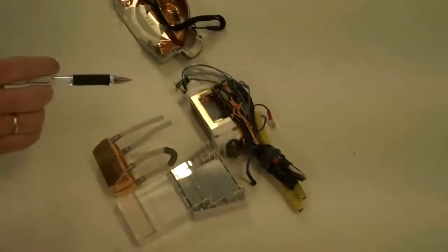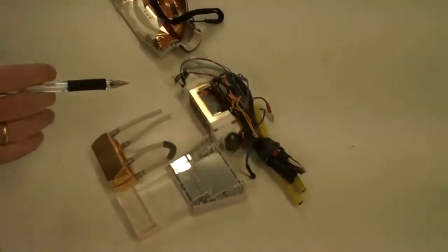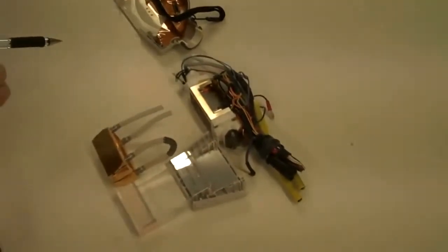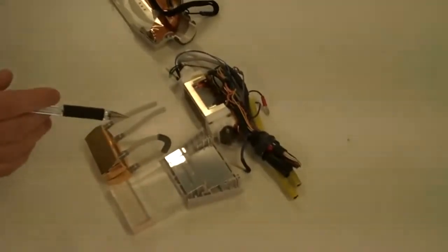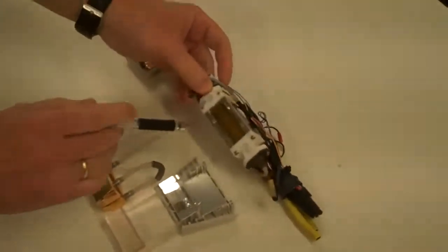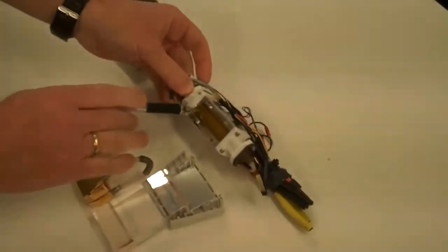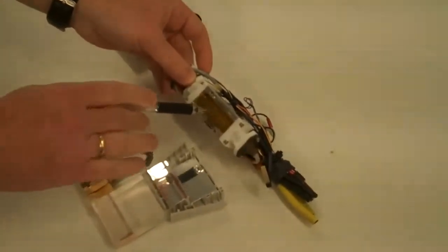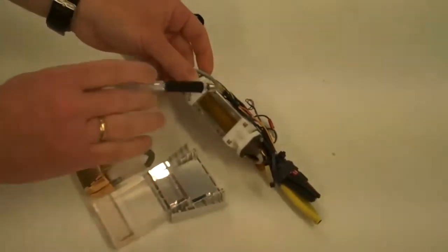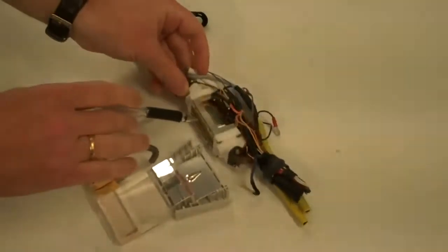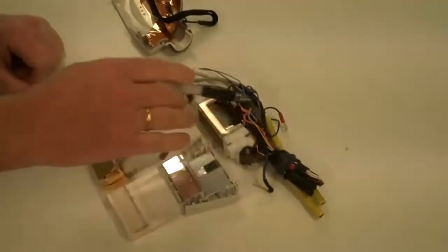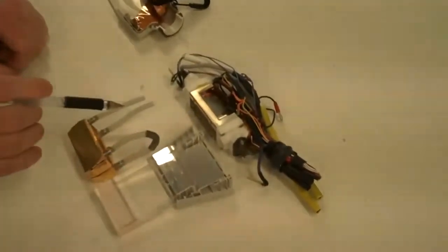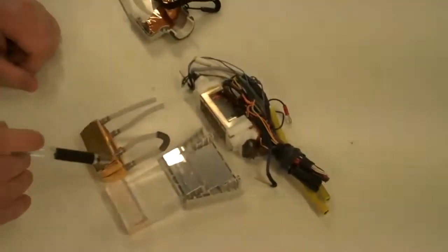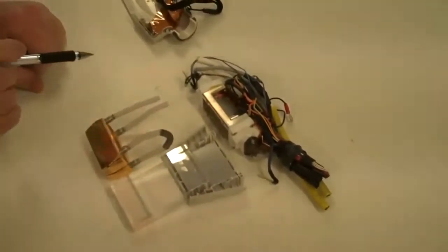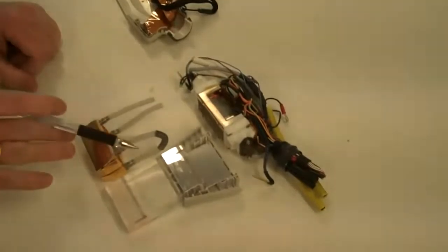In a typical refurbishment of a handpiece, for instance, what a third party would only do would be to replace the internal lamp itself, which again, as mentioned previously, is a non-genuine Palomar lamp. But as you can see, there are other components within the system itself, which include your fluidics and so on, which are not repaired, which are not looked at at all.